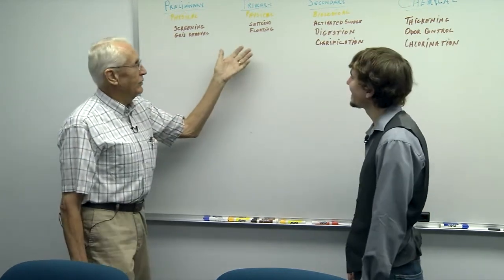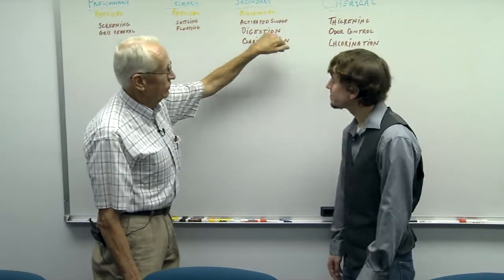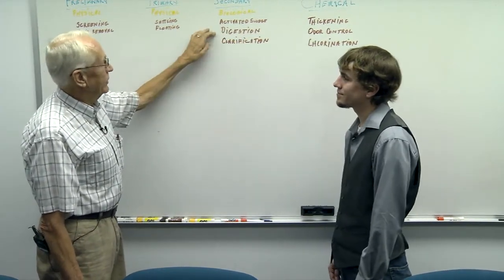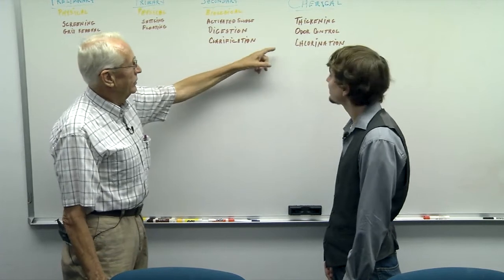And then it goes to the primary system so that it can come into that quiescent stage, which allows the settling and the floating to occur. We go into our biological treatment system, which is the activated sludge. We take that sludge, thicken it, so the process is sort of running back and forth. We thicken it and we bring it back to digestion, and after digestion we remove it by liquid haulers right now. The clarified effluent, which is the final product, is clear, it's chlorinated, and then sent down to the wetlands treatment system for its final treatment part.